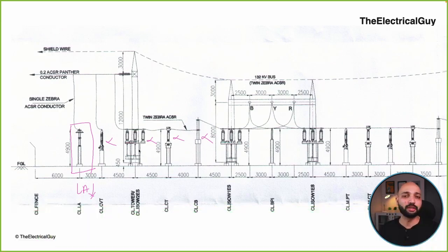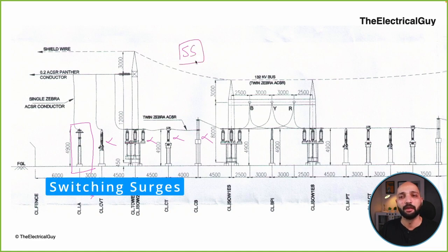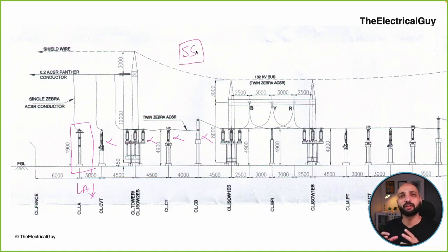The second important function is that it also protects the equipment from switching surges, which are similar to lightning surges. The behavior of switching surge and lightning surge are quite similar, and hence you will also find lightning arrestors installed just next to the key and expensive equipment like the transformer, and this lightning arrestor is connected in parallel in the system. The first equipment that you will see in a substation is the lightning arrestor. This is also a very frequently asked question in technical interviews: what is the first equipment that you will see in the substation? And the answer is the lightning arrestor.